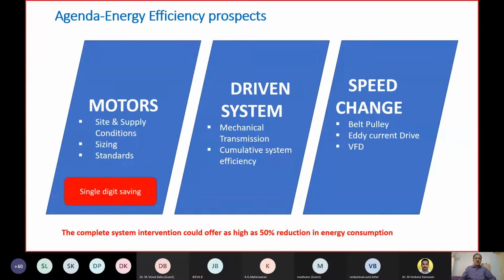So typically within the motor, when we reduce self losses, the energy saving opportunity available is a single-digit saving. Whereas in the case of the driven system and speed change, double-digit energy saving is possible. So therefore, without belittling or dismissing motors as not so important, we have to build a case for including motors. Although single-digit saving is possible by replacing motors, we have to include the quantum of reliability and energy efficiency that is available through motors, through reduction of their own self losses. And then we go on to build a case for the driven system and speed change.